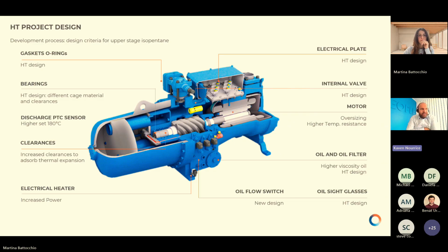Basically, everything changed, excluding the external casing, the external cast iron. The main pillars of the development were a different motor that withstands higher temperature with oversizing of the windings, the oil and everything related to it, so the oil flow switch, the oil filter, the oil sight glasses, and also the electrical heater, because it needed to heat up more than the standard process. Also the clearances to withstand and absorb the thermal expansion at this very high temperature.